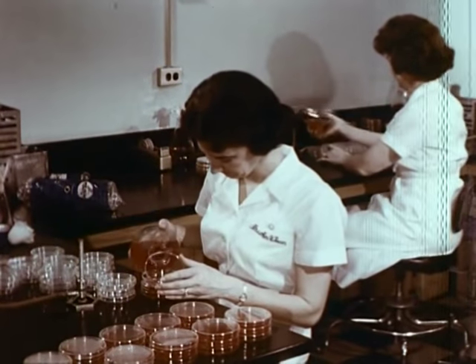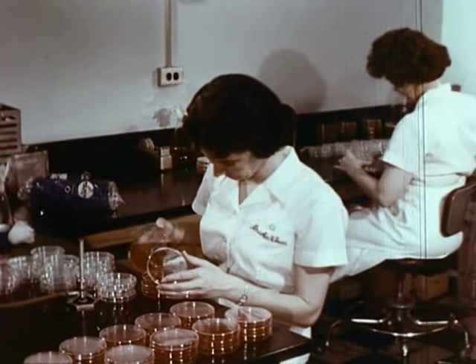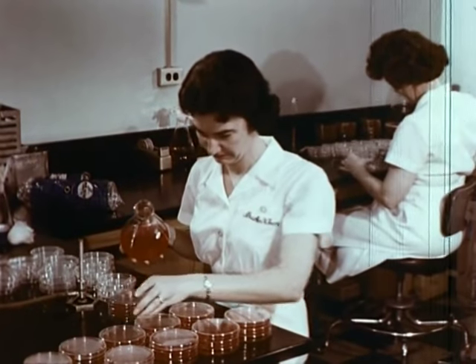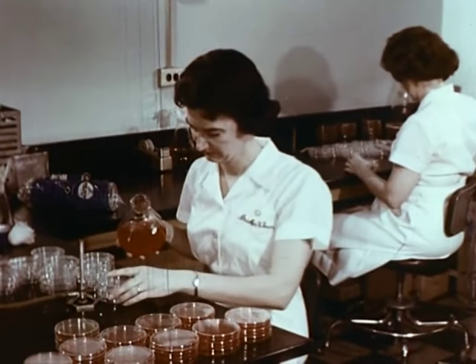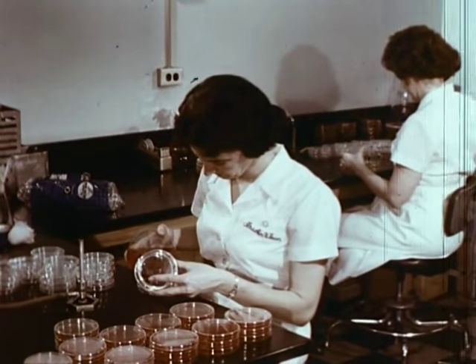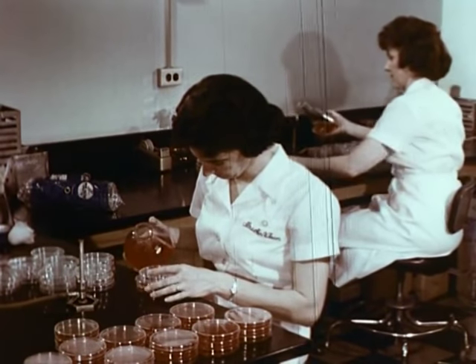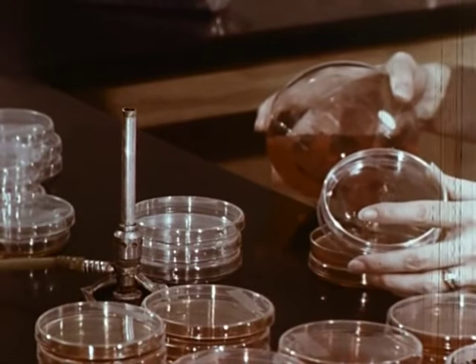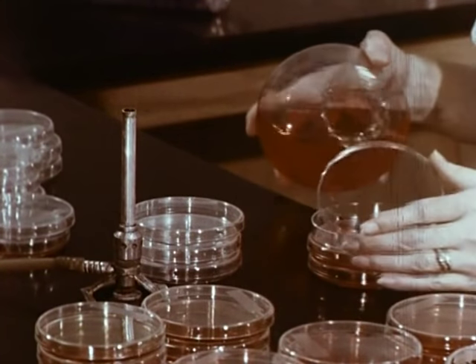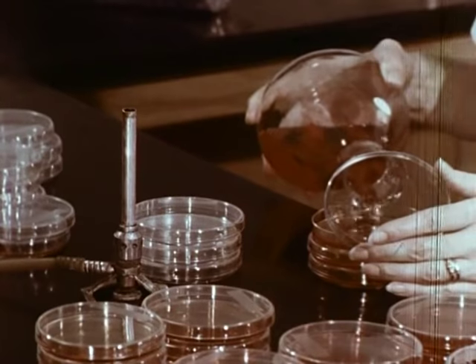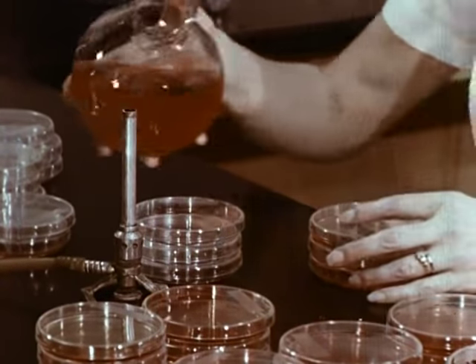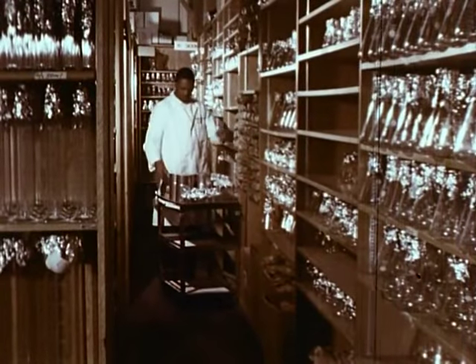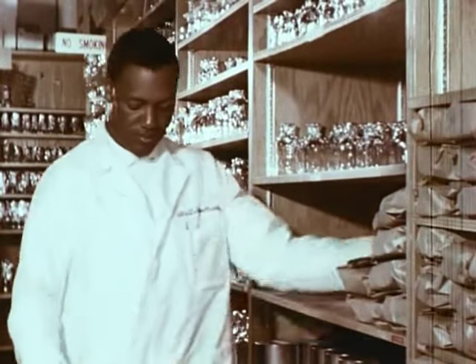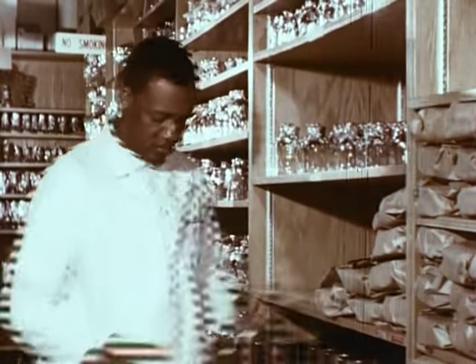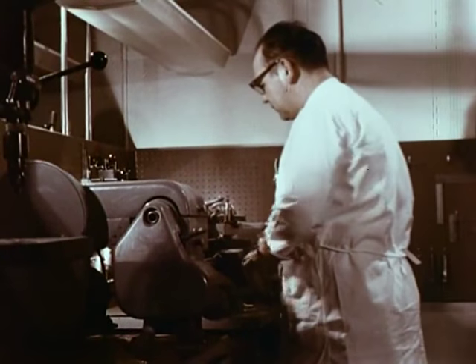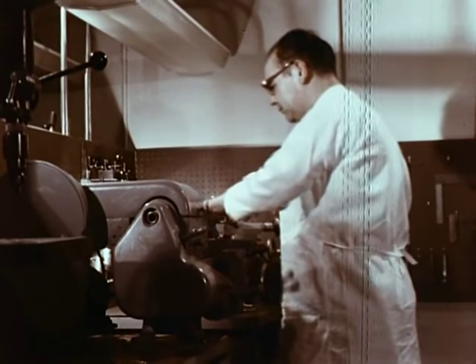Another lab support activity is the preparation of culture media. The room for this should have a controlled movement of filtered supply air during the pouring of the plates and the preparation of other sterile media. To limit the ingress of microorganisms, air in the room always should be maintained at positive pressure to the other lab support rooms. An adequate storage room should be provided for glassware, animal cages, and other equipment, as well as a small machine and glass repair shop.